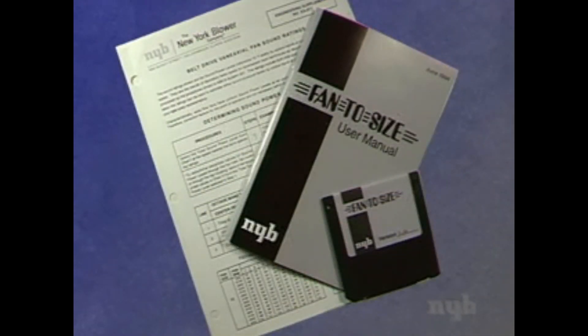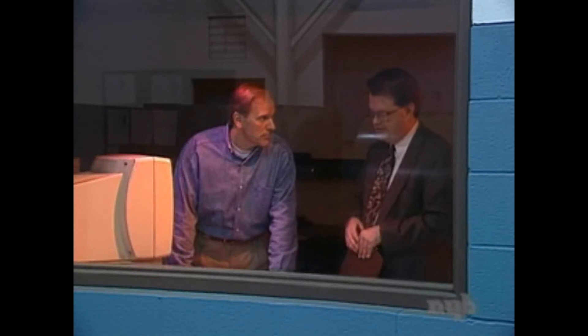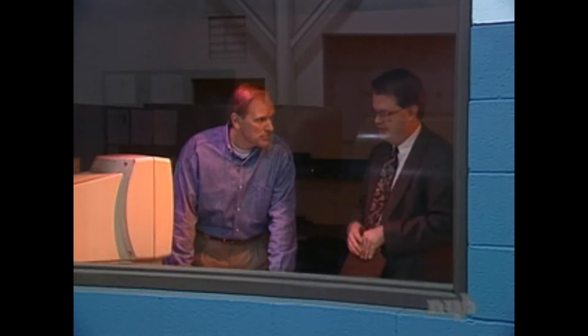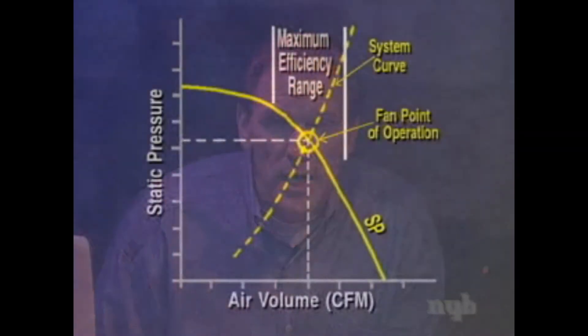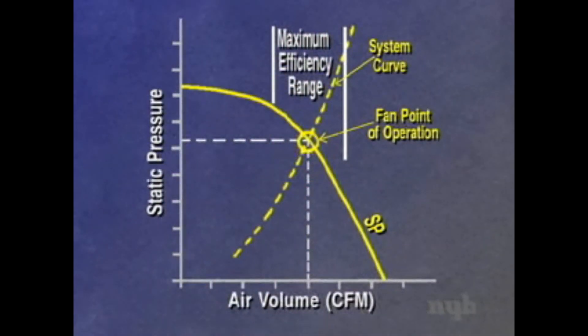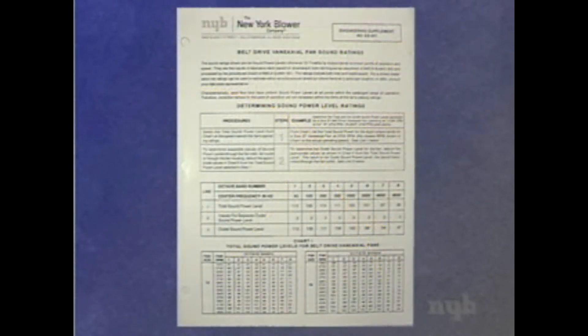New York Blower's fan sound data is available in printed or software formats. The test setup conforms to AMCA Standard 300. Today's setup is Type B, which has a free inlet and ducted outlet, typical for this type of fan equipment. In general, fan sound ratings are calculated in the maximum efficiency range for the fan. When the fan is operating at a point outside of this range, sound rating corrections must be made. These factors are available in the published engineering supplements.